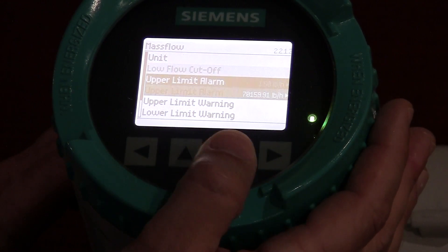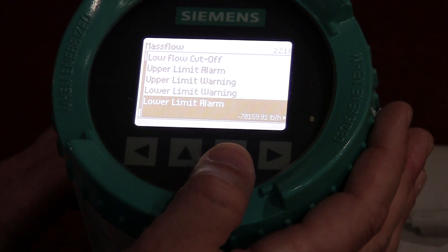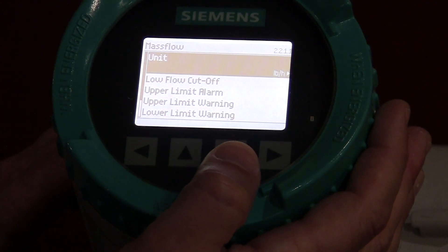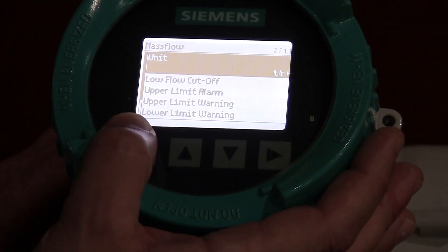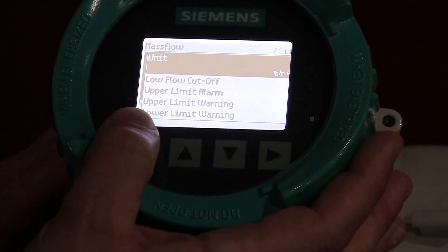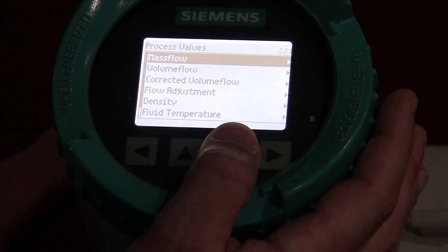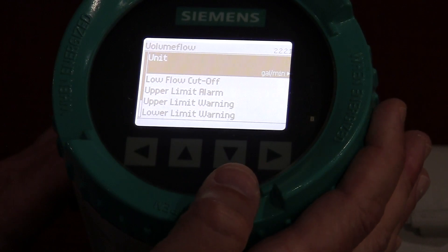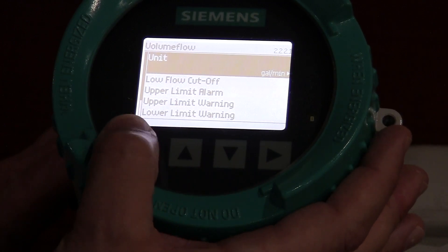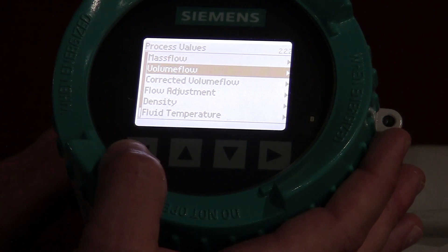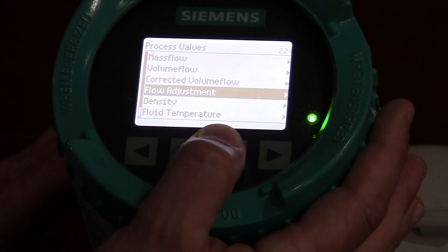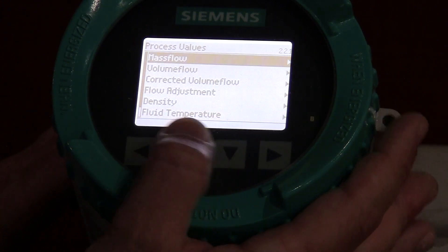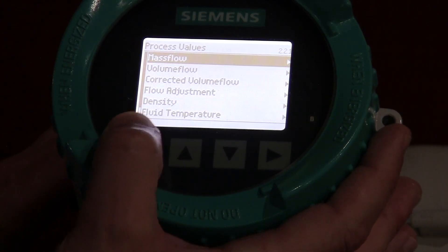And then you can see all the different capabilities you have here for soft alarming. If you want to have an alarm based on either a high or low limit, these are all configurable through that menu, and I can do that for all my values. So if I go down to volume flow, you'll see in this case I'm reading in gallons per minute. You can do that for each of the process variables — same thing for density, temperature. You can arrow through all these setups, basically setting up all the values you want to read in the engineering units that make the most sense for you.